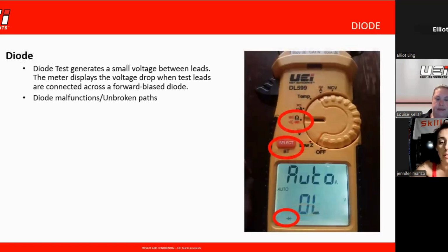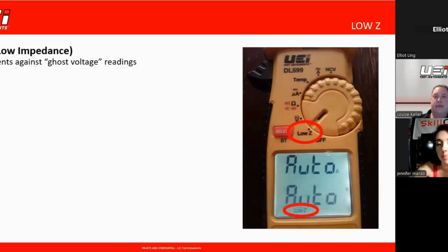This is so necessary, you guys. I can't tell you how many tech support calls I get per day because people are chasing low voltage shorts and getting a bunch of ghost voltage. They're not getting real readings. They're like, why am I reading 12 volts on a 120 volt circuit? Well, you're not—it's ghost voltage.